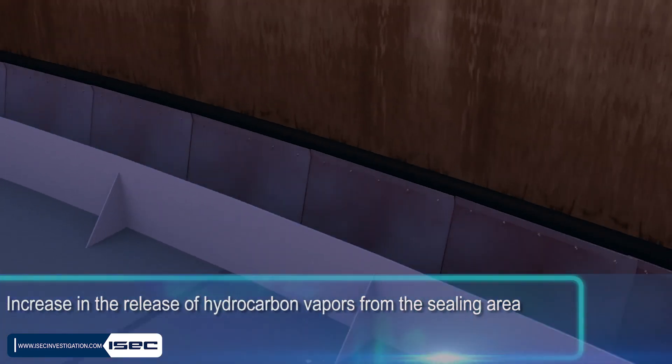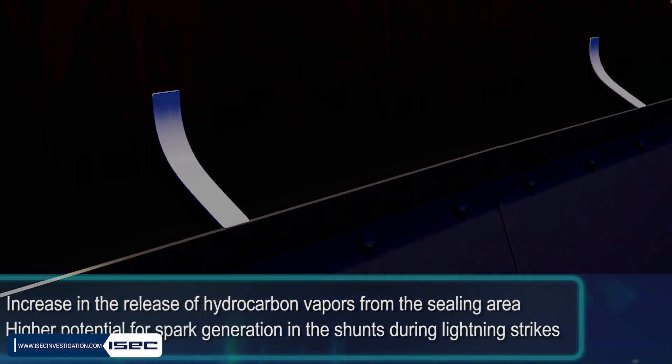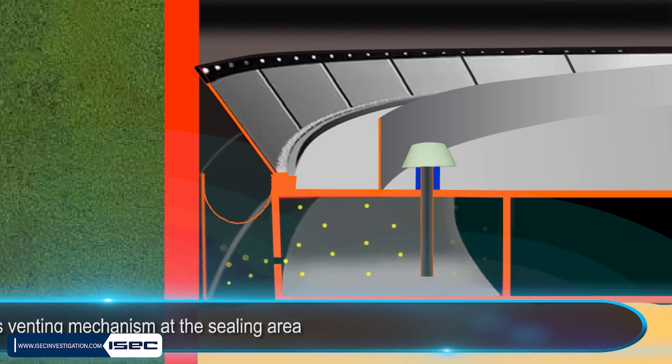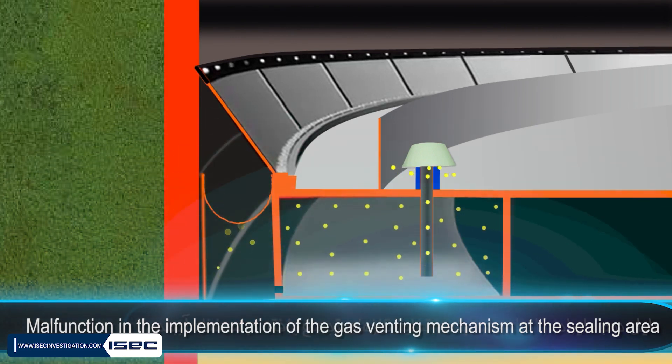This deformation led to two major consequences: first, an increase in the release of hydrocarbon vapors from the sealing area, and second, a higher potential for spark generation in the shunts during lightning strikes. According to post-accident investigations, a malfunction in the implementation of the gas venting mechanism at the sealing area was identified as another contributing factor to the accident.